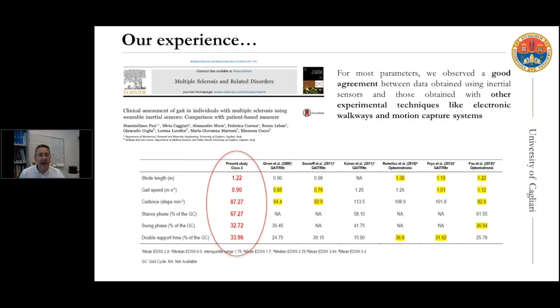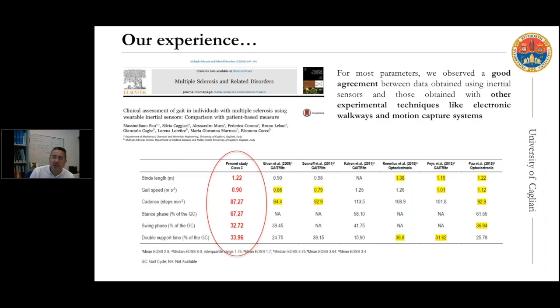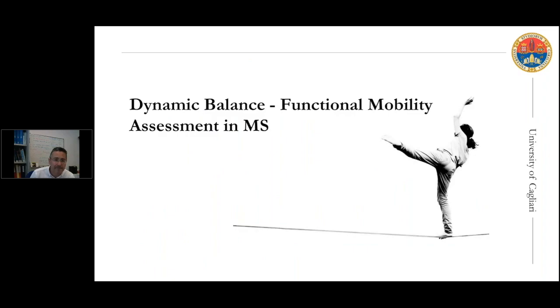It is also important to highlight that we performed a comparison between results obtained with the inertial sensor and results obtained with independent techniques — namely electronic walkways like the GAITRite, very commonly used in neurological gait assessment, and also with optoelectronic systems, meaning classical three-dimensional gait analysis with motion capture. Most of the parameters measured with the inertial sensor were in very good agreement with those measured with the other independent techniques.